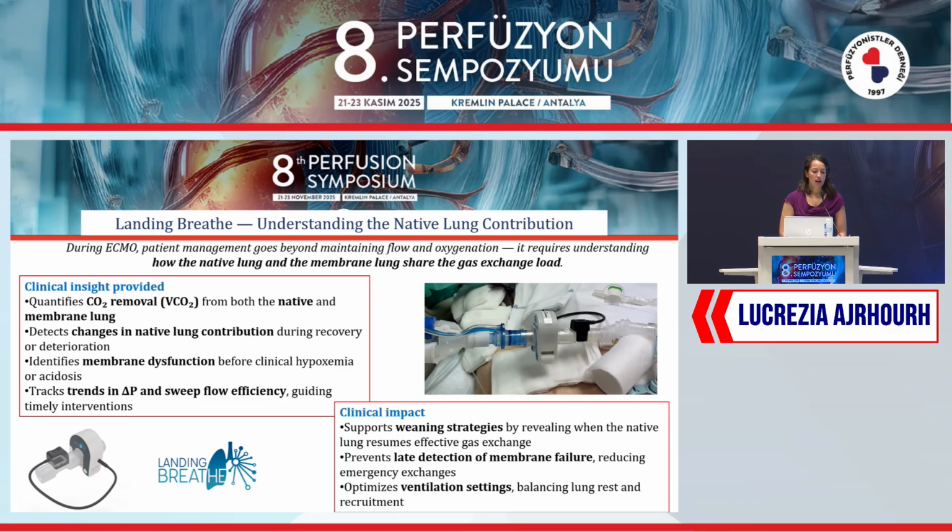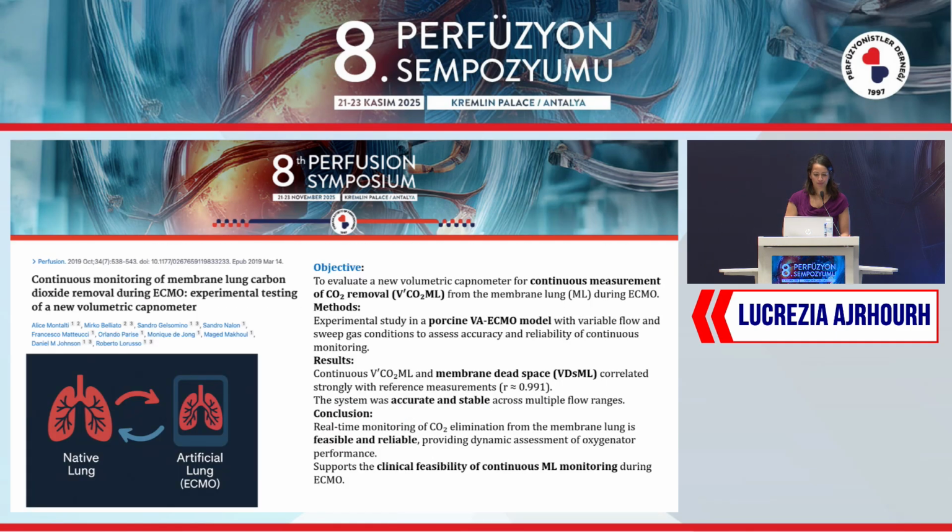So we have a lot of clinical insight provided: quantify CO2 removal from both the native and membrane lung, detect changes in native lung contribution, identify membrane dysfunction, and trend pressure drop and sweep flow efficiency. There's an important clinical impact because it supports weaning strategy, prevents late detection of membrane failure, and optimizes ventilation settings.